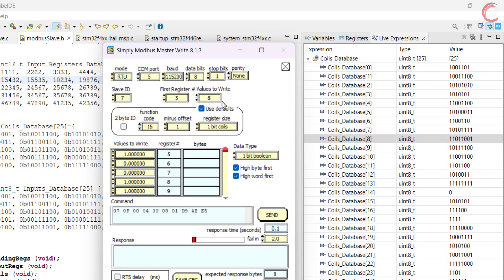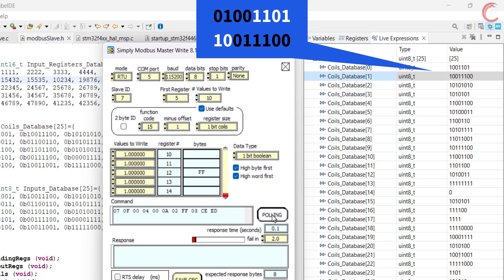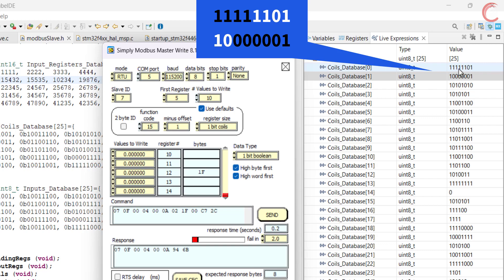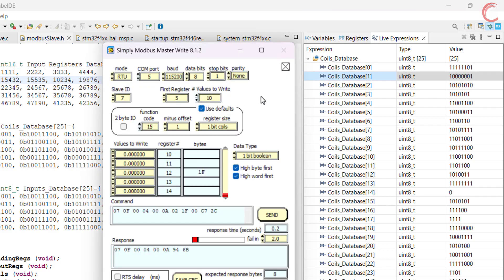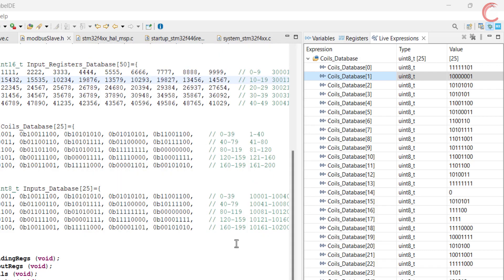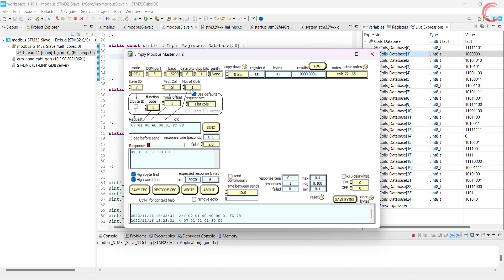Now let's say the master wants to write 10 bits starting from the 5th coil, sending 1 for each coil. This is the 5th coil where the modification will start, and you can see the modified values. Let me change some of these bits to 0s. Here you can see the updated result for the 10 coils. Before we wrap up, let's read these coils and check the values the master will receive. The master wants to read 10 coils starting from the 5th coil. You can see the data received contains 5 ones and 5 zeros — this is indeed the updated value.